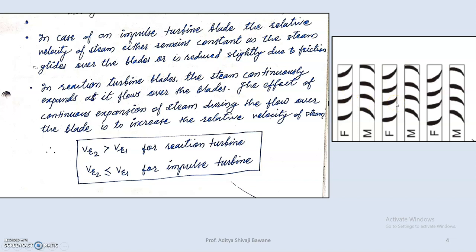In the case of a reaction turbine, whenever steam moves over the fixed and moving blades it continuously expands due to the aerofoil shape. The effect of this continuous expansion of steam during flow over the blade is to increase the relative velocity of steam. So in a reaction turbine the relative velocity goes on increasing. This is the distinguishing factor: if relative velocity is greater at outlet it is a reaction turbine; if it is smaller at outlet it is an impulse turbine.